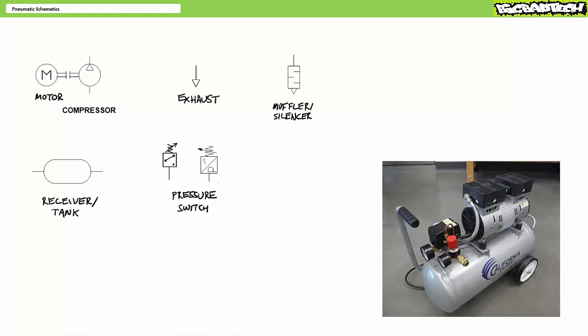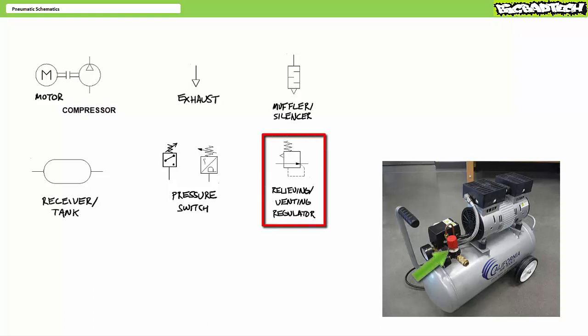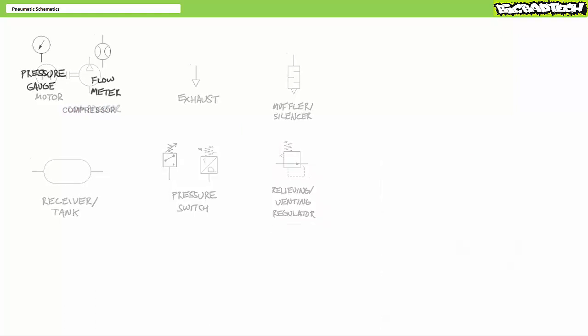More advanced systems might make use of a pressure transducer, which is an analog device which measures pressure. Lastly, a regulator selectively opens and closes the passage from the receiver to the pneumatic circuit. If a regulator is venting or relieving, it includes an exhaust port back to atmosphere and sometimes may use a bi-directional arrow.